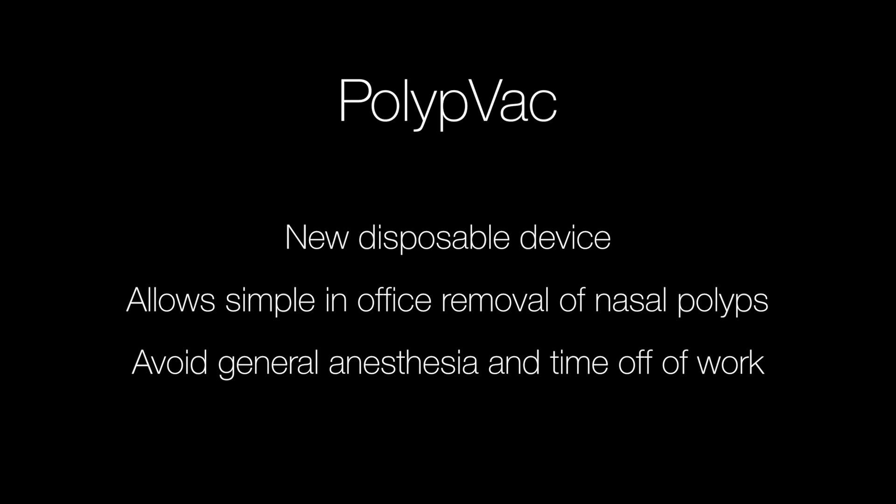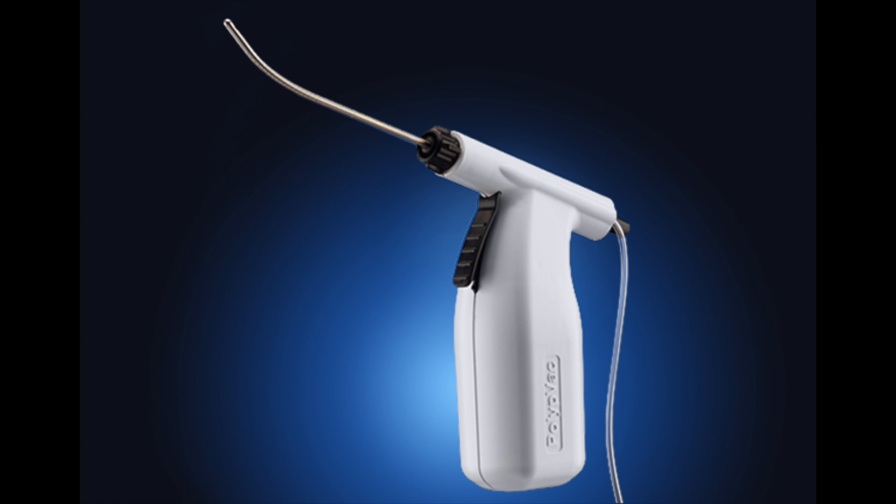Here we can see the PolypVac device. It is self-contained. It does not require any electricity and just gets plugged into your office suction that's part of your ENT cabinet or wall suction.